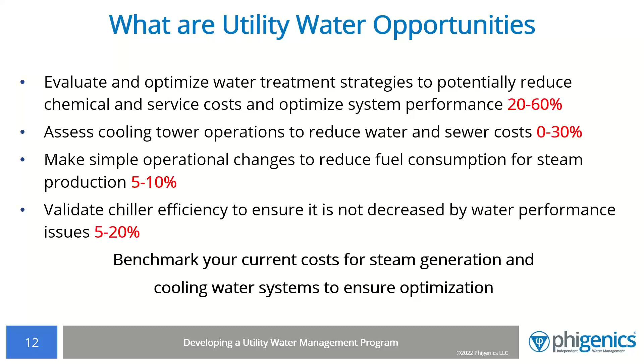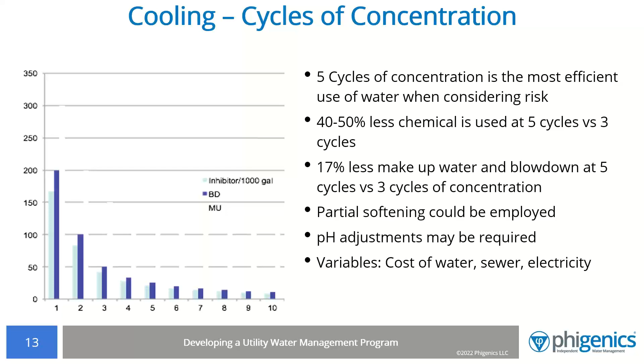So jumping right in, let's talk about cycles of concentration. It never gets old, and why do I say that? It's because no matter how much we talk about it, we always run into facilities that have not optimized it. As you know, cycles of concentration is how many times water flows around the cooling tower loop before it is dumped to waste. You want to optimize the use of the water while taking into consideration the cost of water, sewer, chemicals, energy, and service hours, while ensuring that you're not jeopardizing the lifespan of the equipment. We see far too many systems where facilities are spending 2 to 3 times as much as they should be on cooling tower operations.